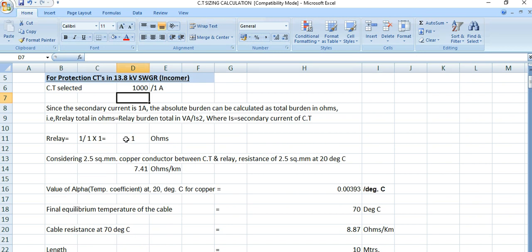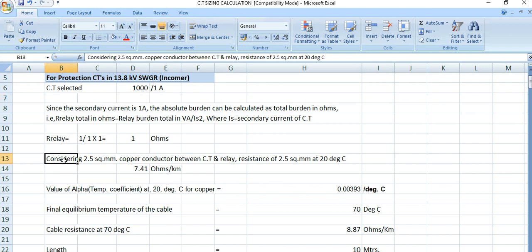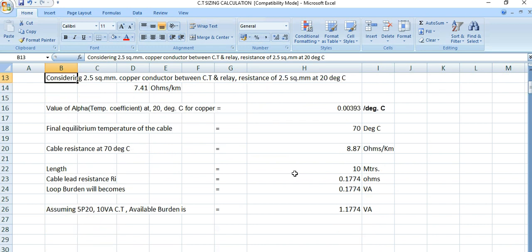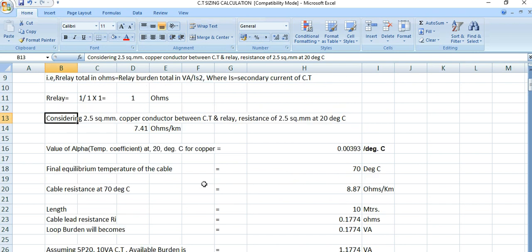Before proceeding, let's brief the procedure. For CT dimensioning or protection CT sizing, there are two things we need to check. First, we need to calculate the lead resistance — the conductor that will be connected with the CT, preferably 2.5 square mm copper conductor. The second thing is the relay burden, which also needs to be considered.